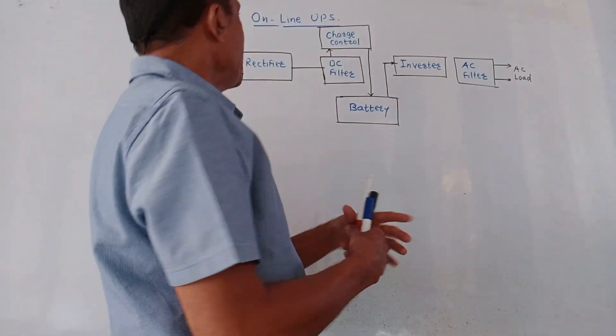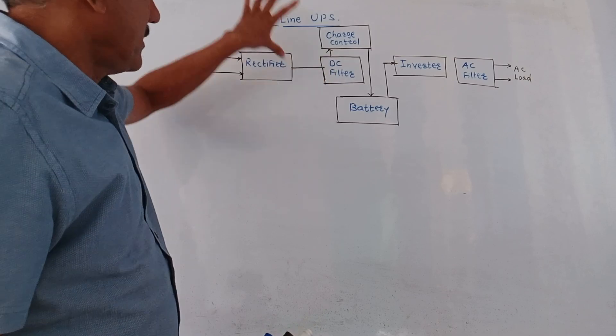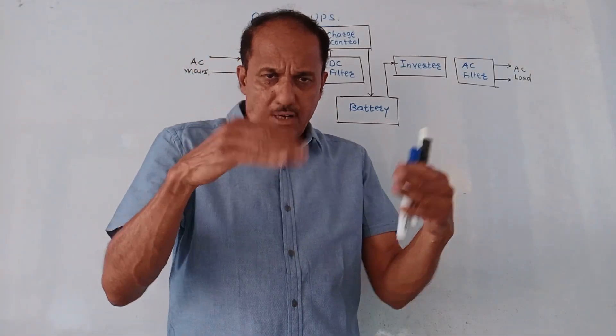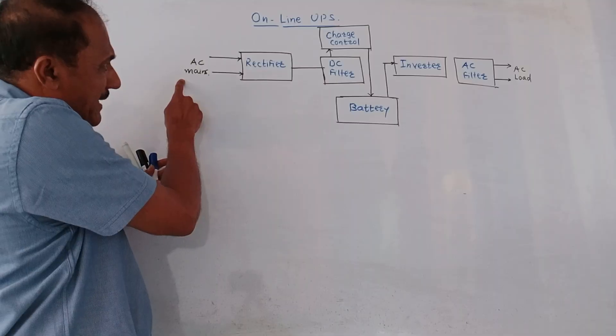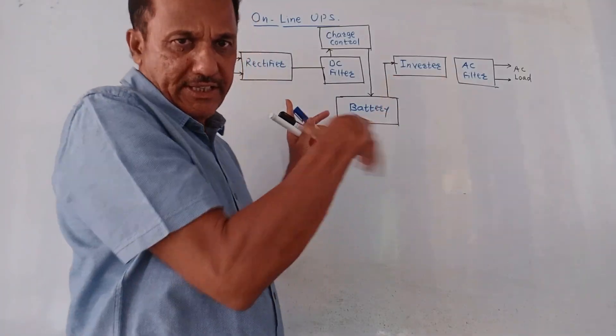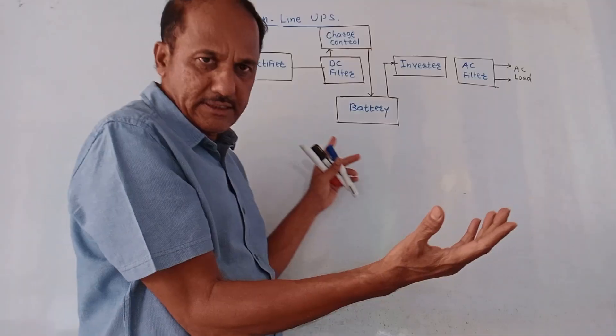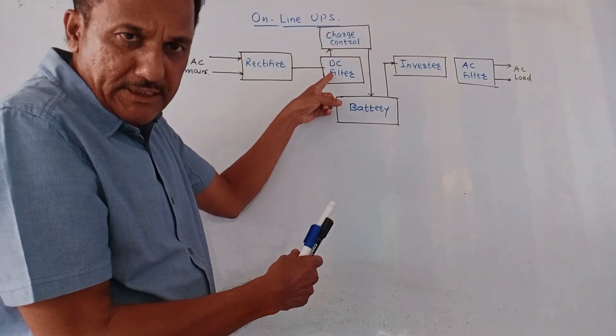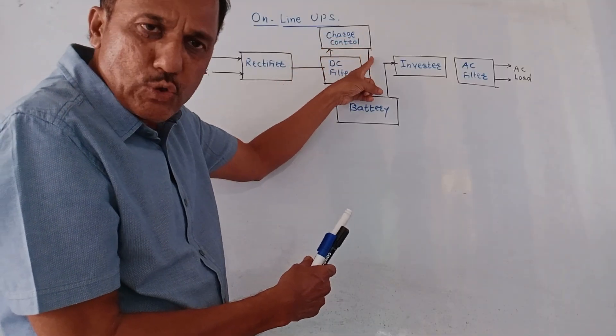The next part is online UPS. As the name indicates, the UPS is always connected to the main supply. AC mains output is given to the rectifier, which converts it into DC. Then we use a DC filter, and its output is given to the charge control unit, which is directly connected to the battery. Charging of the battery is controlled whenever the power supply is connected.